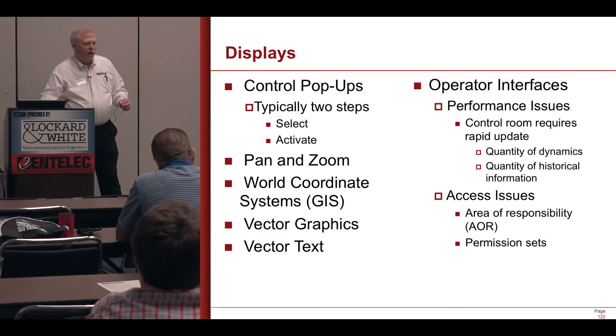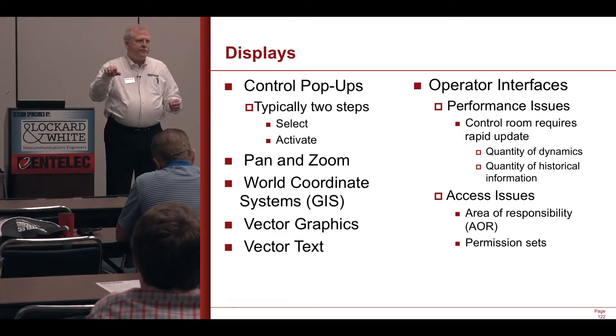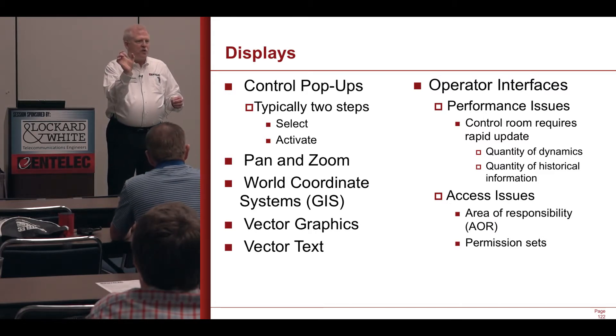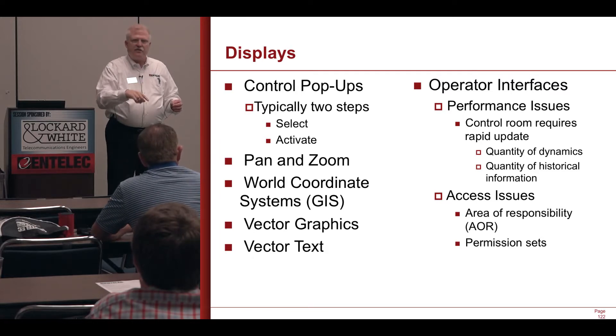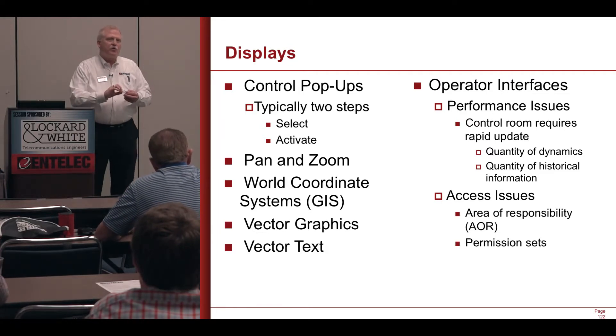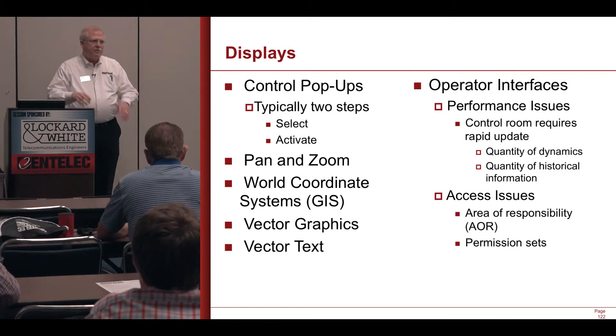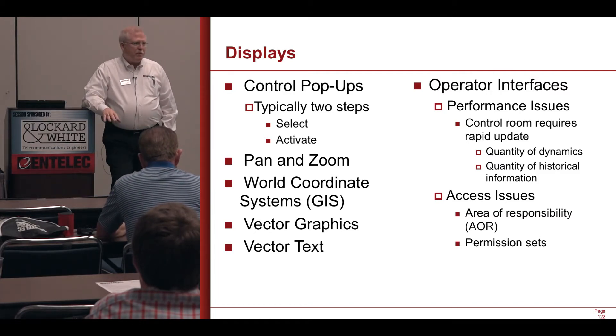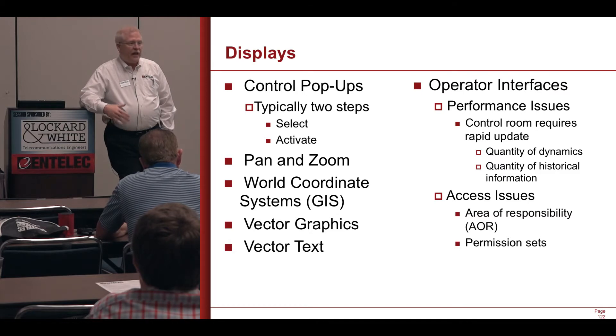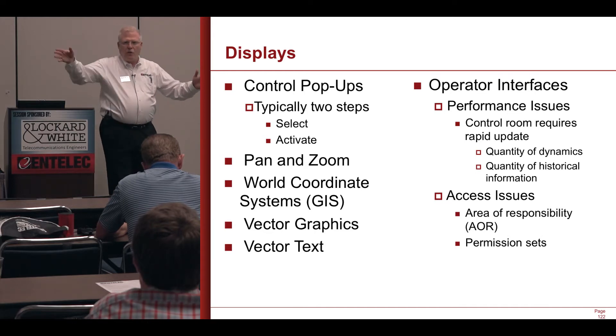You also want to do what's called select-before-operate: I want to control this flow controller to 100 M a day — click — you want to control this controller to 100 M a day, correct? Yes — click. That's select-before-operate; in other words, verify before you write. There are a lot of cool tools SCADA vendors put in like pan and zoom, built-in maps, and all that — but maps are better in a GIS system, not in a SCADA system. What a SCADA controller needs is an overview perspective. They don't really care geographically if it's north or south; what they care about is upstream or downstream. So when we build screens, everything to the extent we can is left to right, like reading a book.